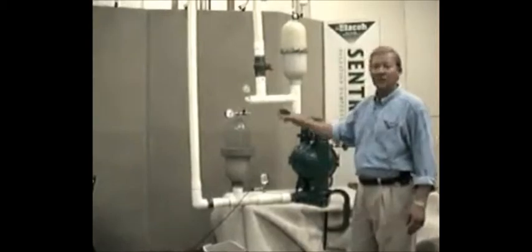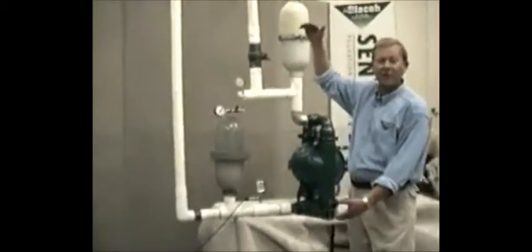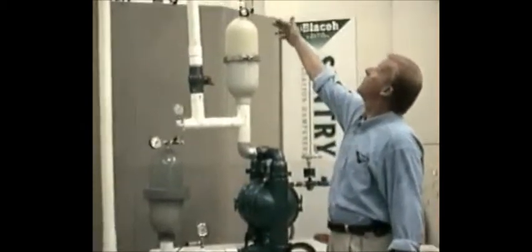This simulates a tall tank feeding the inlet to the pump, and we've accomplished this by using a forklift with a tub of water approximately 12 feet in the air.